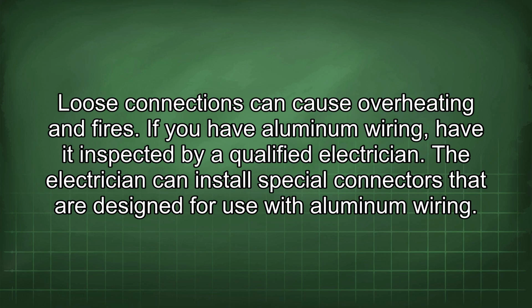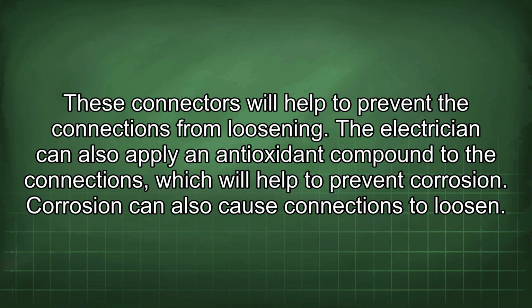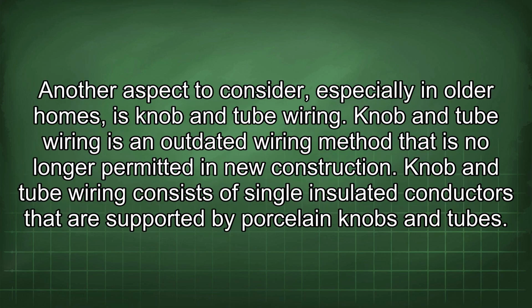The electrician can install special connectors that are designed for use with aluminum wiring. These connectors will help to prevent the connections from loosening. The electrician can also apply an antioxidant compound to the connections, which will help to prevent corrosion. Corrosion can also cause connections to loosen. Another aspect to consider, especially in older homes, is knob and tube wiring. Knob and tube wiring is an outdated wiring method that is no longer permitted in new construction.